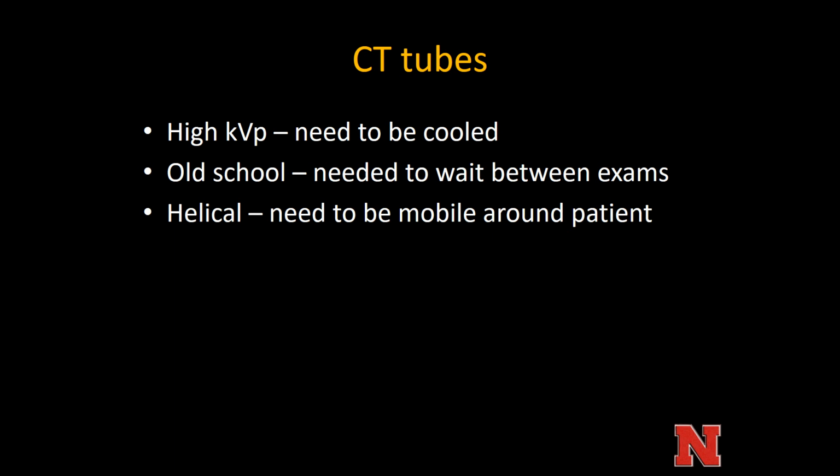CT tubes generally have among the higher kVps. They need to be cooled. Old school, you would actually have to wait in between exams for the whole setup to cool down. Boy, wouldn't it have been nice to be a radiologist back then. You could just do a CT, read it, and then you don't get another CT for 15 to 20 minutes because the tube had to cool down. In most modern units, you don't have to wait like that any longer. Helical scans need to be mobile around the patient. When you get into the actual CT lecture, there will be discussions about the specifications needed to alter the tube to do helical scanning, kind of beyond this talk.